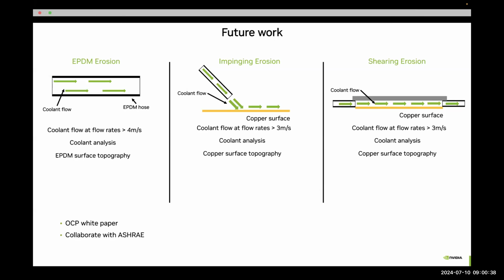And should we say this only for the cold plate, or should we say it for any copper tube that is in the data center loop? Really, it should extend to anything in the loop. But that is another clarification. I'm trying to work with ASHRAE to clarify, because the current guidance is actually 1.5 meters per second for the flexible hosing. But there are nuances to that, because there's going to be the fluid velocity of the cold plate, and then there's also the fluid velocity of the secondary piping, the row manifold, etc. So that is another clarification that does need to come across.